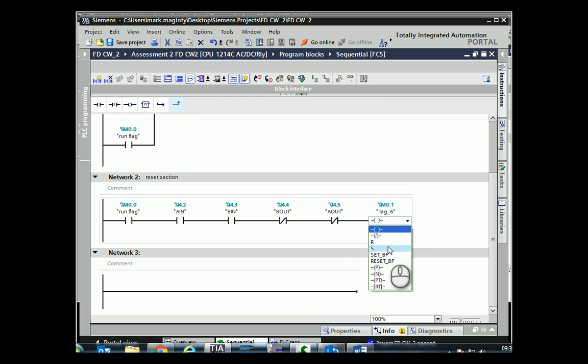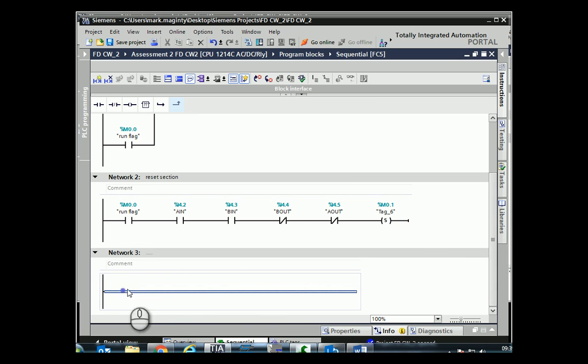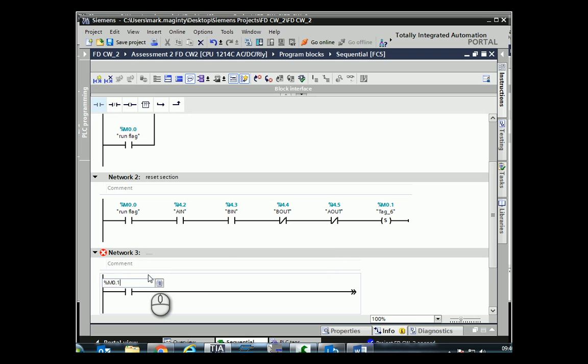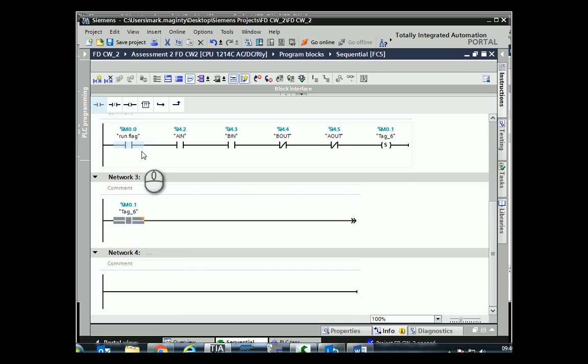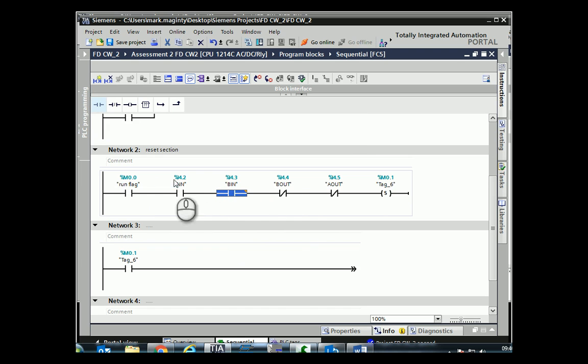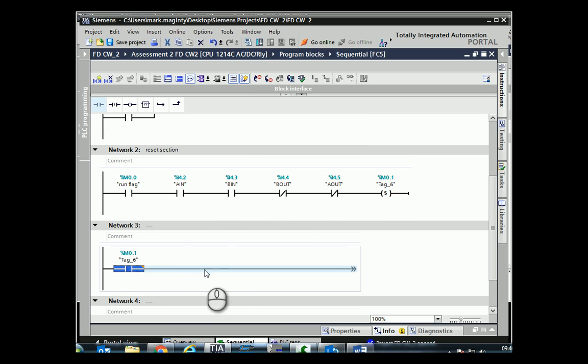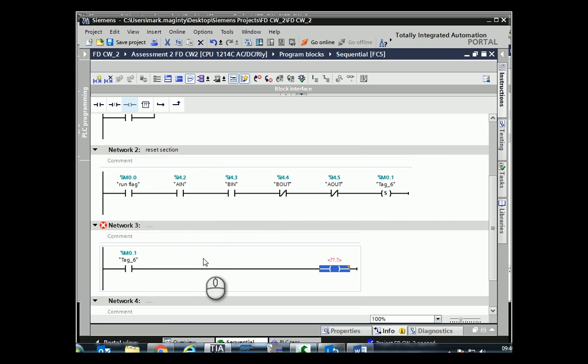Here we actually change this to a SET instruction. The next line works on the same basic principle: when M0.1 is activated, the first thing in the sequence is A+ should happen. So far: we press start, the run flag turns on, the machine is deemed to be in the reset position by those four conditions, it sets M0.1, and as long as M0.1 is active it will SET A+ to go out.